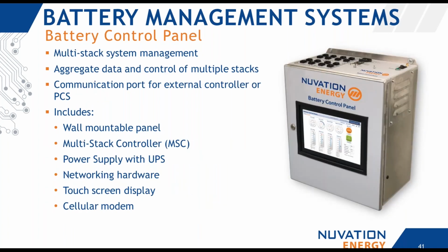And at the multi-stack level, this is our battery control panel. So this aggregates data and control of multiple stacks. It's going to be communicating with the external controller, or PCS. That external controller doesn't need to worry about how many stacks are in parallel or what the states of these different stacks are. That's all handled by the battery control panel. It's as if it's a single battery that's being presented. So it simplifies that high level control.